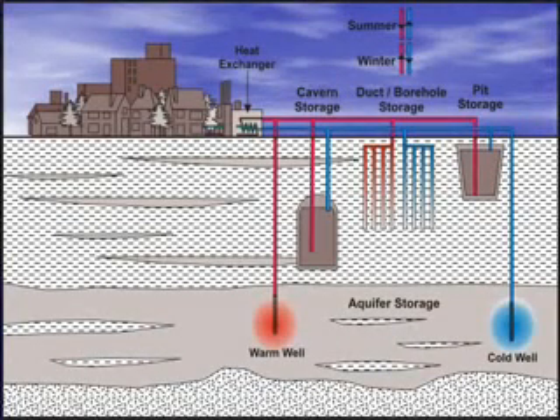If we don't have an aquifer with groundwater readily available, and instead have fine-grained sediments, maybe silts and clays, or a fine-grained glacial till, or maybe a massive crystalline basement complex, a big granite complex or something like that, essentially no water, we can put in a series of boreholes closely spaced, and run piping down within the borehole, back up, connect them all together, and create, in a relatively small area, a thermal energy store. Once again, we can create a hot store and a cold store. You need a lot of boreholes, but you can do it.